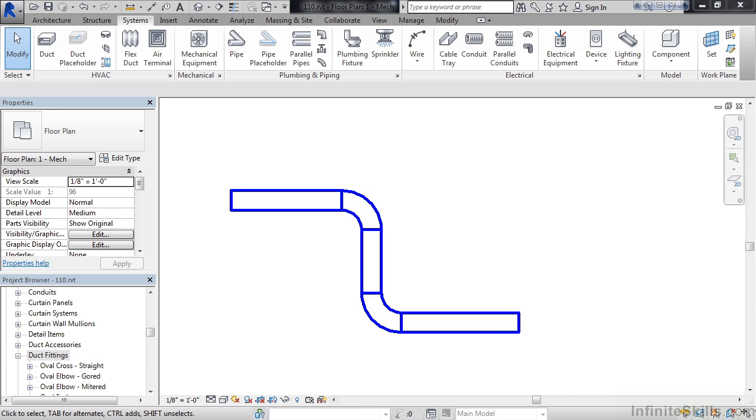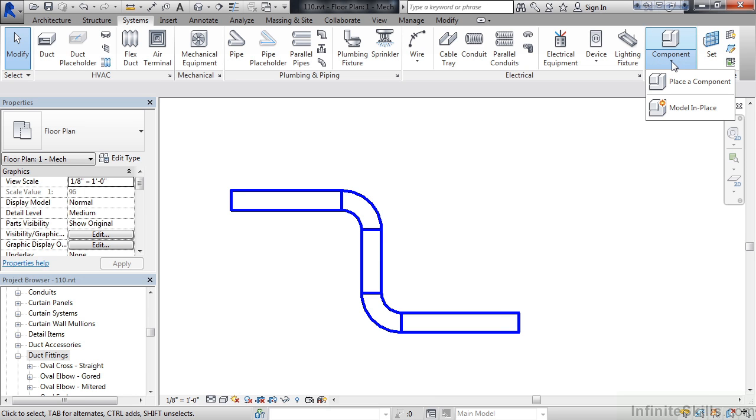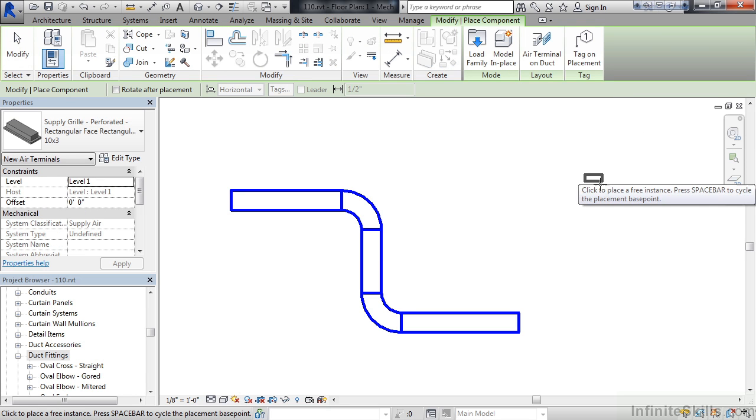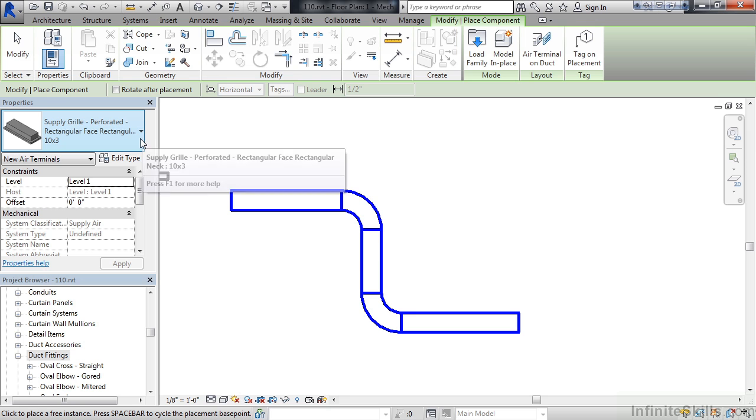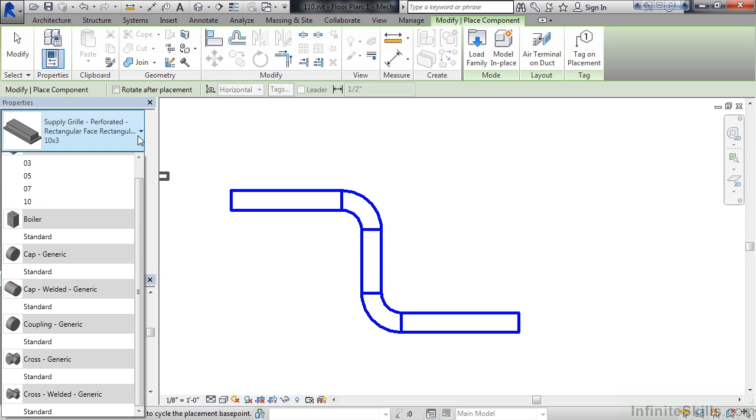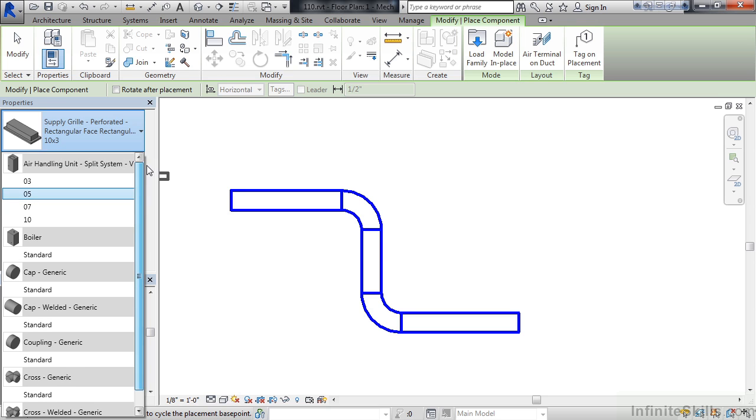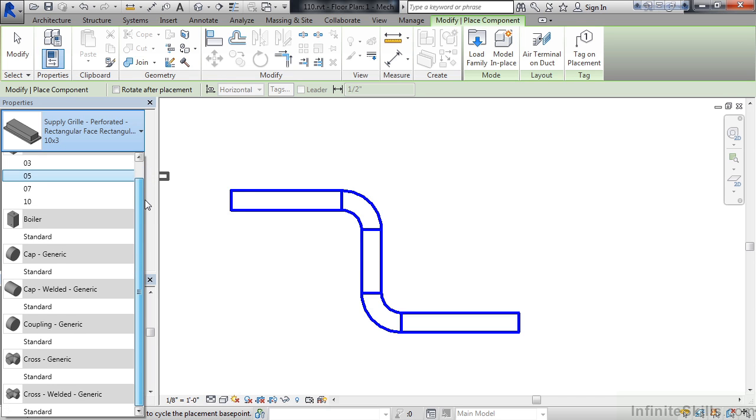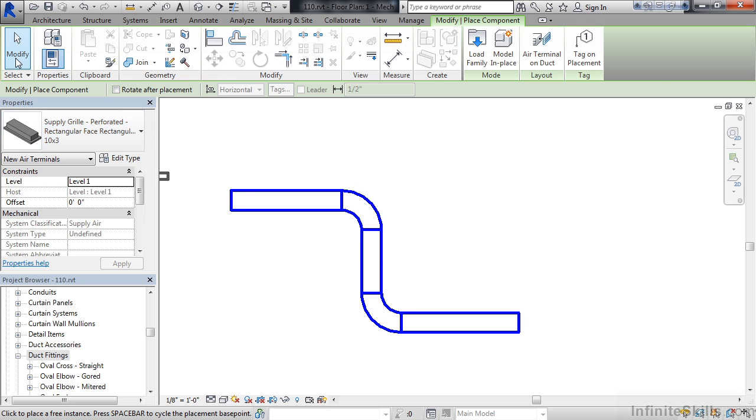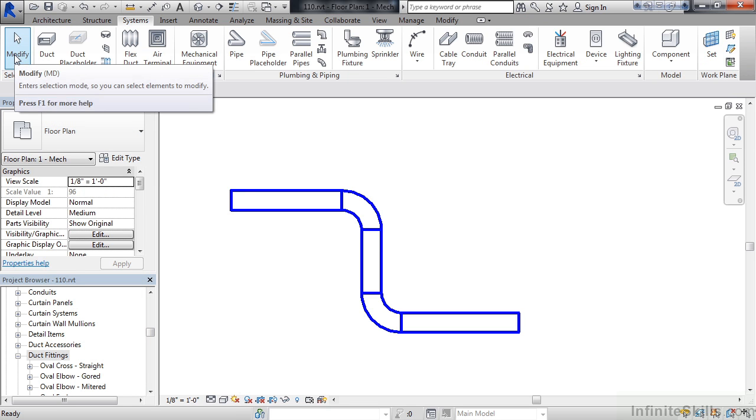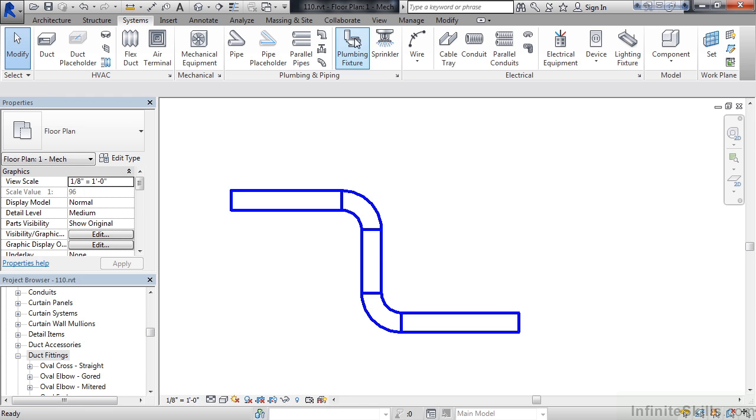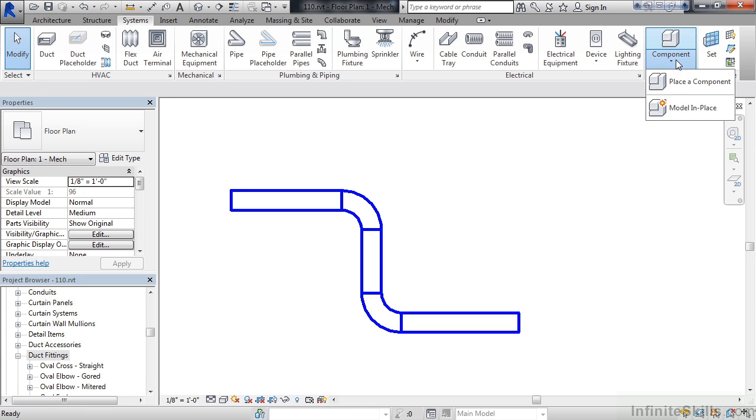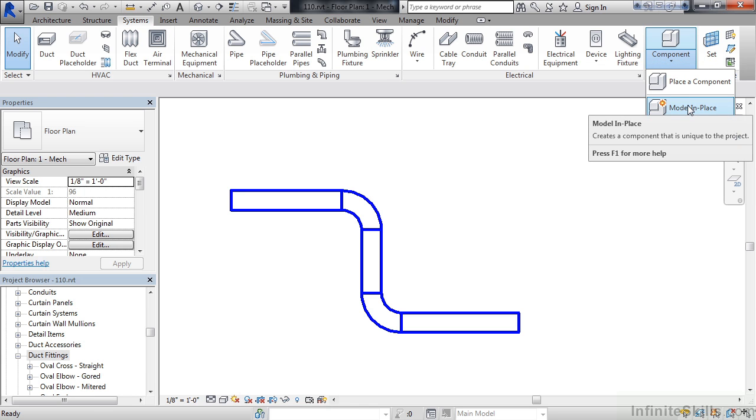First off, you would go to whatever tab for whatever you're designing. In this case, we're in systems. So I'm going to go to the systems tab, then all the way over to the right to component. Now, in the drop-down for component, you have two options. You have the place a component. And just to show that, this is for those elements that already exist that you want to reuse within this project. So once I click place a component, you have the drop-down in properties for the different components that I could place in that match up to this system that I'm placing or something similar to it. Click modify in the upper left to exit out of that. Go back to the systems tab, go all the way to the right to the component drop-down, and click model in place.